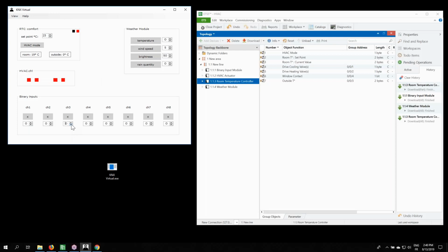Okay, so if I open the window again, then the RTC will stop with this. And that's then the last part of the webinar. Now I'm going to let the temperature in the room drop until 0 degrees. But we will see that there will be a reaction of the RTC. There will be some action that will make sure that the room temperature will not reach 0 degrees. As I said, this is for protecting the building against damage because of frozen water.